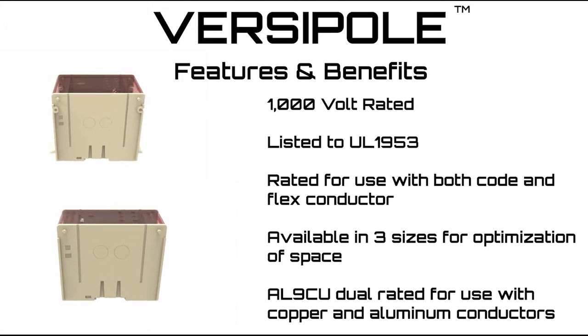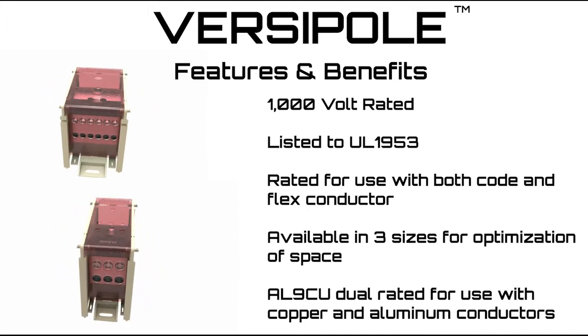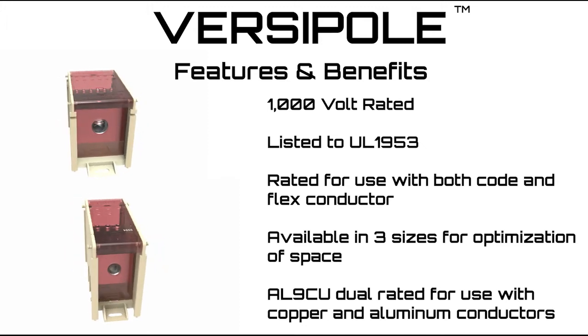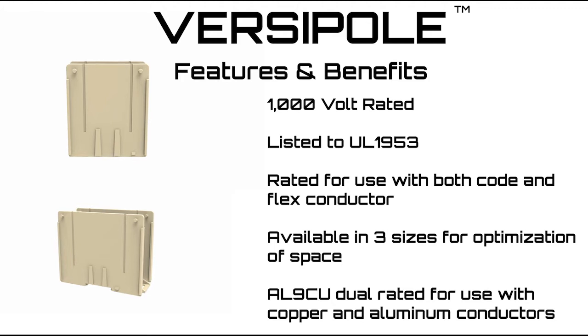All Burndy Versipole Configurable Series Power Distribution Blocks are 1000 Volt rated, listed to UL 1953, rated for use with both code and flex conductors with no ferrules required, and available in three sizes for optimization of space.